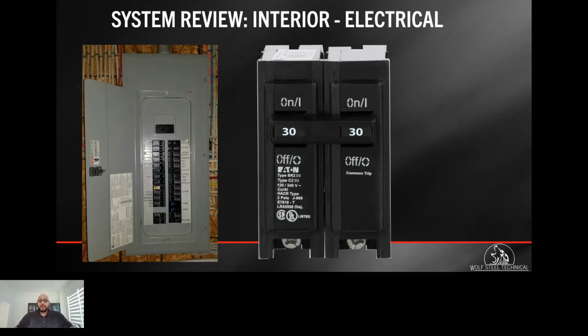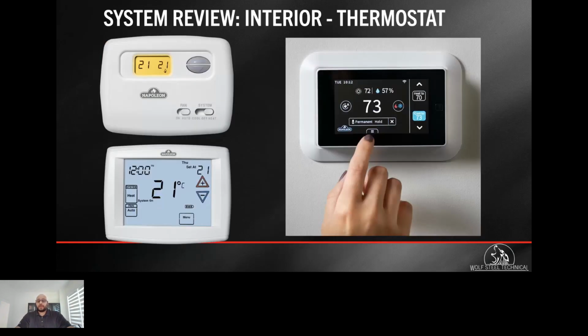And speaking of thermostats, what kind of thermostat does the customer have? We want to ensure that the thermostat the customer is using is able to run hybrid heating. There are thermostats that do several heating and cooling options. At face value, they are cheaper than most smart thermostats, but these thermostats will run your heat pump as a priority and have a timer so that if it's unable to achieve the heat, it will kick in your secondary source of heat. This is not an energy efficient way to run a heat pump.